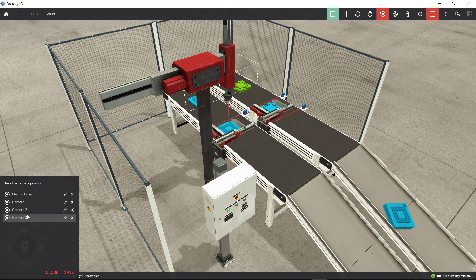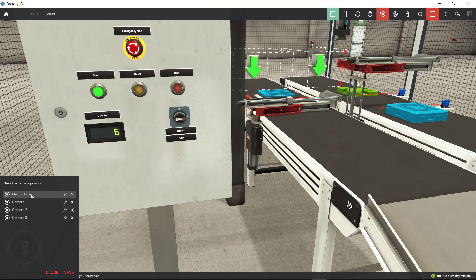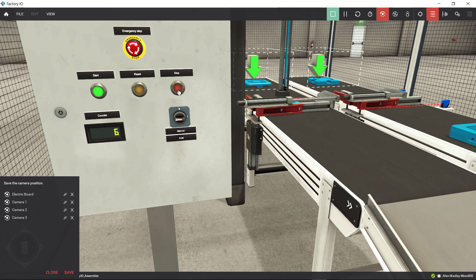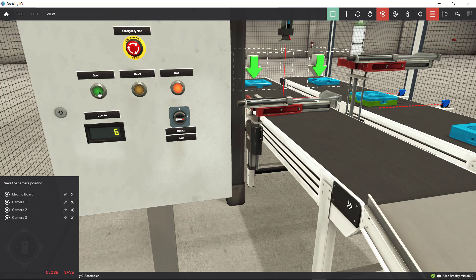Alright, that looks good. But what happens if I press the stop button right now? I pressed the stop button and you notice that the motion continues until the cycle is completed — it doesn't stop right away, it just finishes the current cycle it was in the middle of. That's what the stop button in the code is programmed to do. What will happen if I click start again? The clamp has to go down and the conveyor has to move — let's see if that's the behavior we want. Let's press the start button.